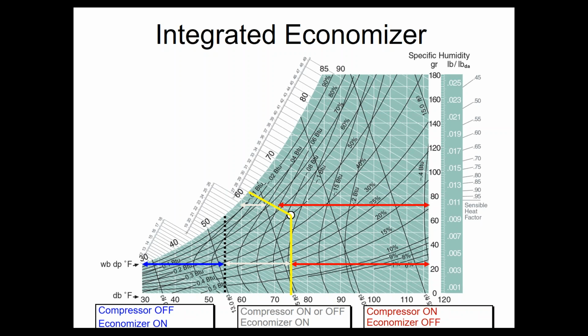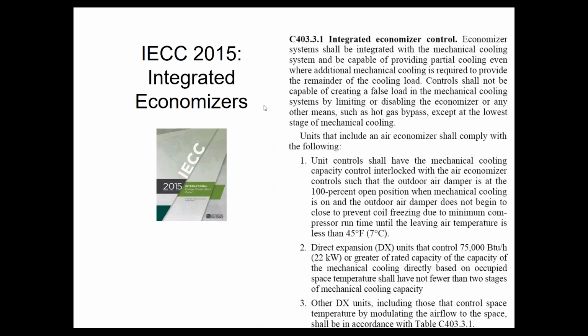Andy asks clarification on integrated economizer. This means 100% OA without refrigeration down to 55 degrees dry. So here's the definition of what integrated economizer means. The unit shall have the mechanical cooling capacity to get down to 100%, with the damper 100% open, get down to the full cooling load.